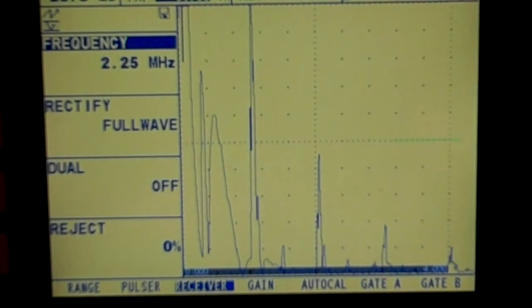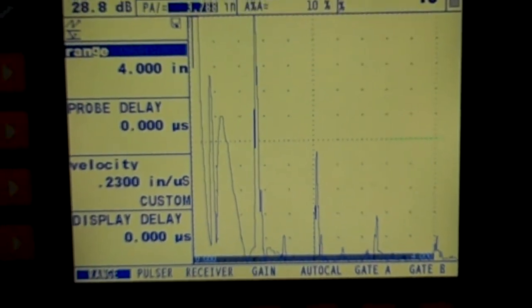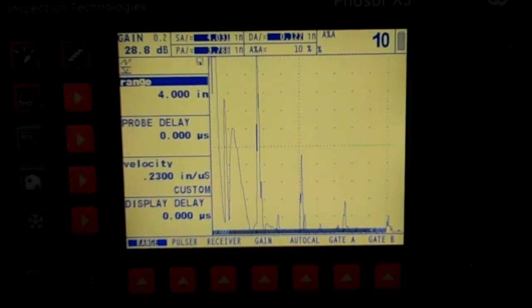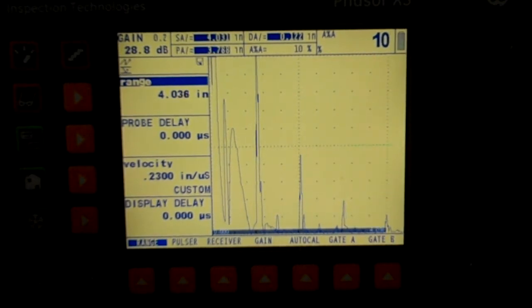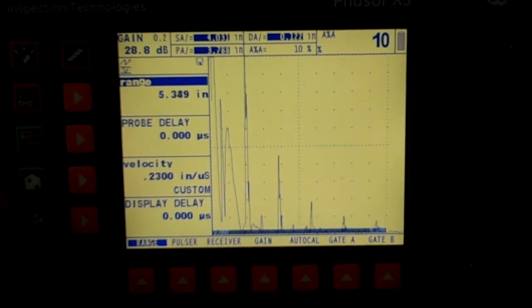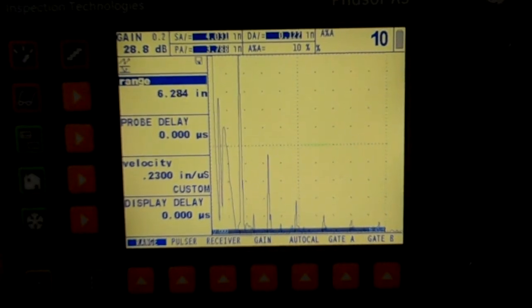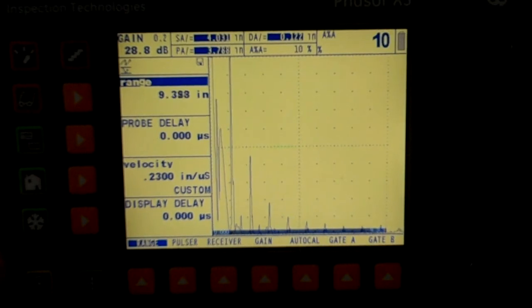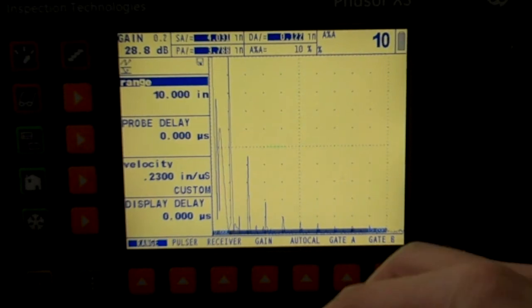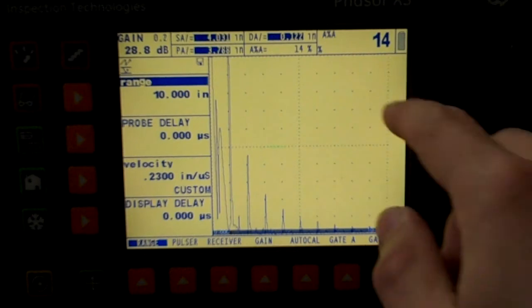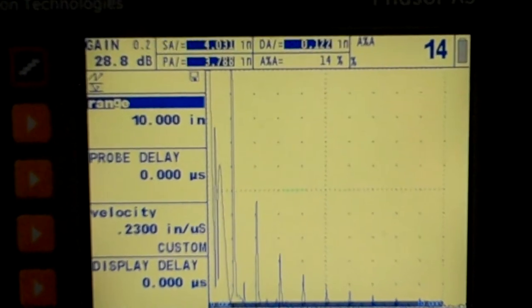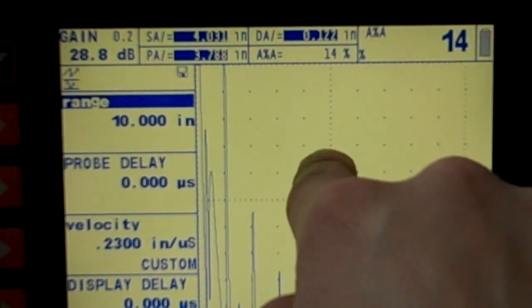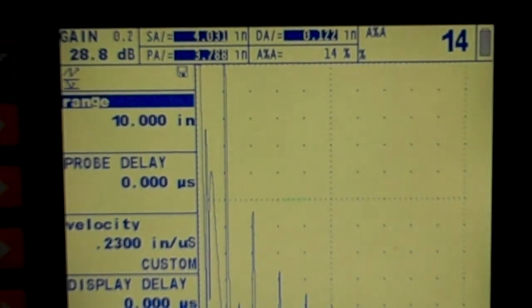So I'm going to go back to range. I pushed the range button. Let's back out a little bit so you can see the buttons I'm pushing. So there's our range button. Lab 1 says to establish a 10 inch range. We're on a 4 inch range, so we just need to take our range to 10 inches. Now we should have a signal at 1, 2, 3, 4, 5, 6, 7, 8, 9, 10. So that means each one of these screen divisions, let's zoom back in a little bit, each one of these screen divisions, 1 inch, 2 inch, 3, 4, 5, 6, 7, 8, 9, 10.